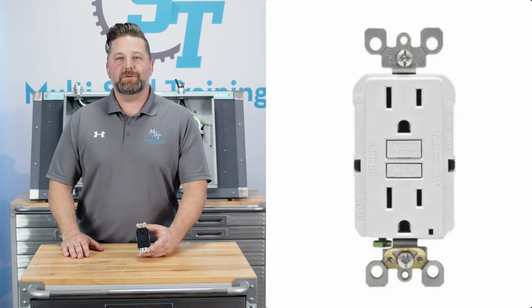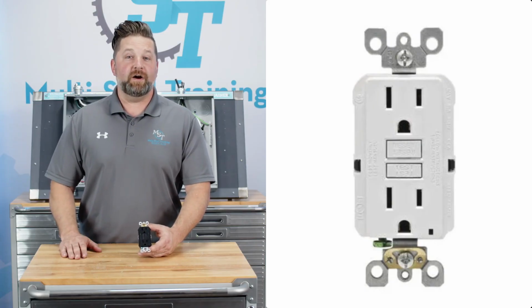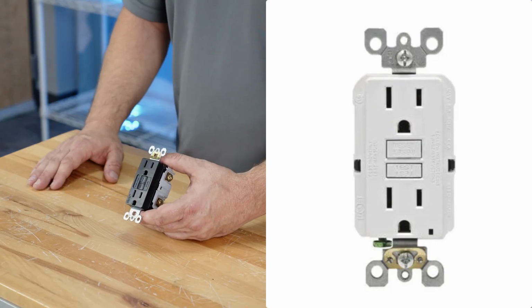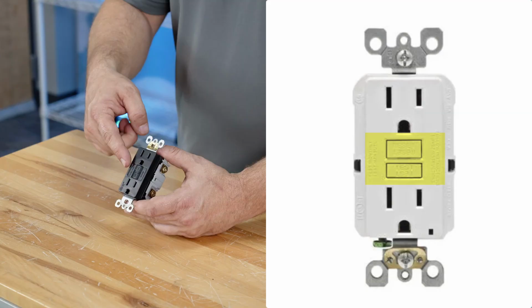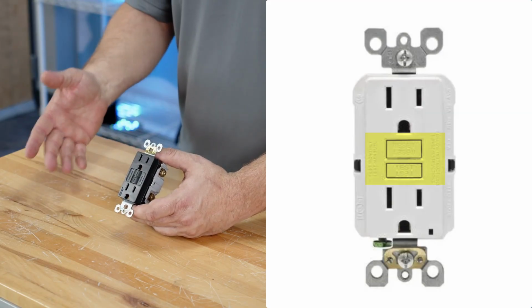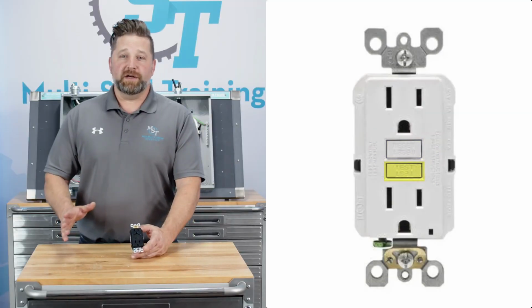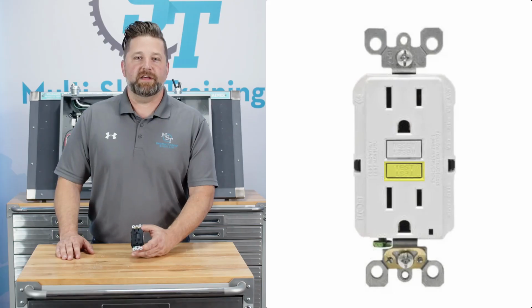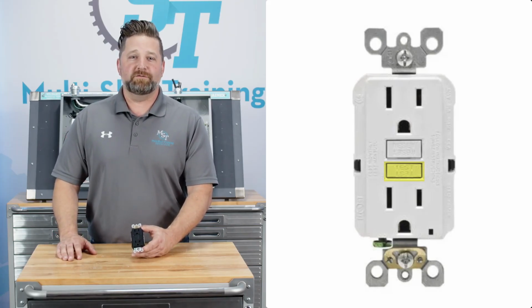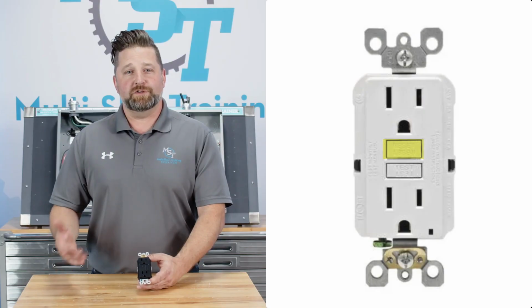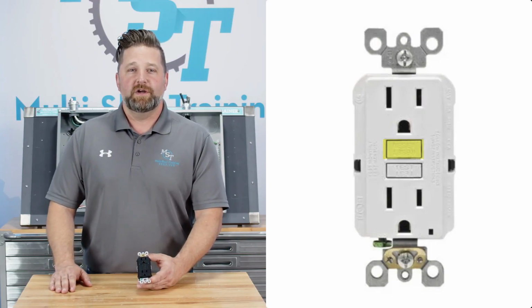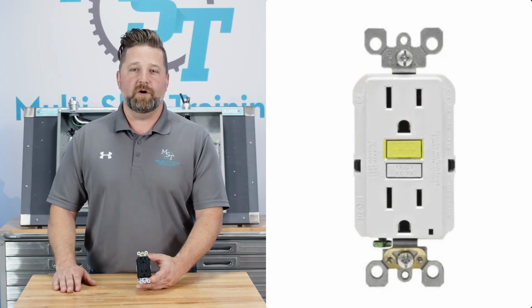The most common type of GFCI device is a GFCI outlet receptacle, which resembles a standard duplex outlet but has 2 buttons in the center, a test button and a reset button. The test button is used to test the outlet. Pressing it simulates a ground fault and should cause the outlet to trip, cutting power. The reset button restores power after the outlet trips, whether due to testing or an actual fault.